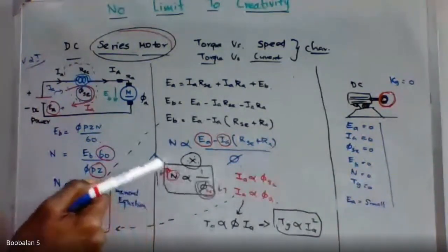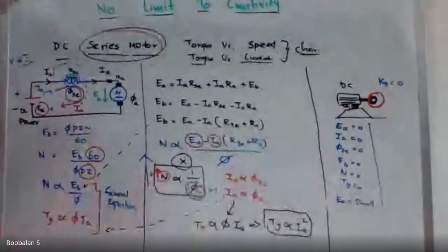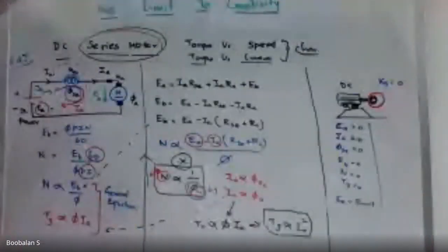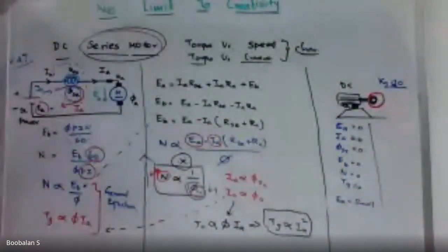That's called inversely proportional. If we start without applying a load, the speed is very high and we can't control the motor, and the motor would fly off its bed. So to avoid this, before applying voltage they apply a minimum mechanical load, 20 kg or 30 kg, or 10 kg, based upon the motor weight and rating.